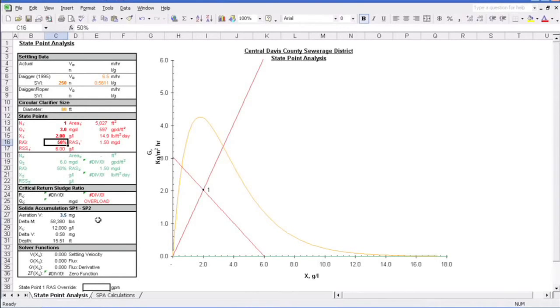As we mentioned earlier, a lower RAS flow results in a flatter underflow rate line, so let's change that. In this case, we can drop our RAS to about 30% or 0.9MGD and still be under the line. Does this mean we should always drop the RAS down such that we are as close to the settling curve as possible? Actually, no.